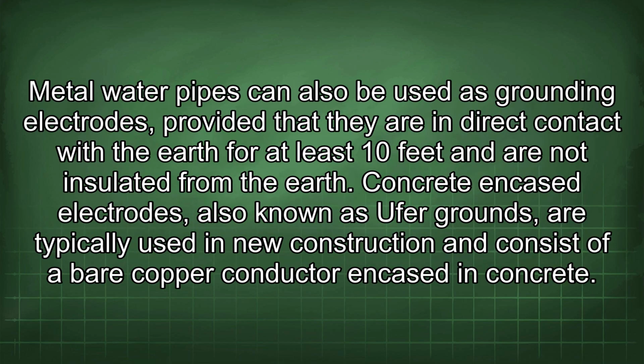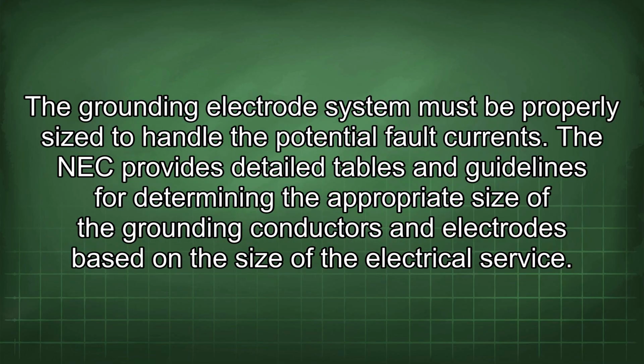Metal water pipes can also be used as grounding electrodes, provided that they are in direct contact with the earth for at least 10 feet and are not insulated from the earth. Concrete encased electrodes, also known as UFER grounds, are typically used in new construction and consist of a bare copper conductor encased in concrete. The grounding electrode system must be properly sized to handle the potential fault currents. The NEC provides detailed tables and guidelines for determining the appropriate size of the grounding conductors and electrodes based on the size of the electrical service.